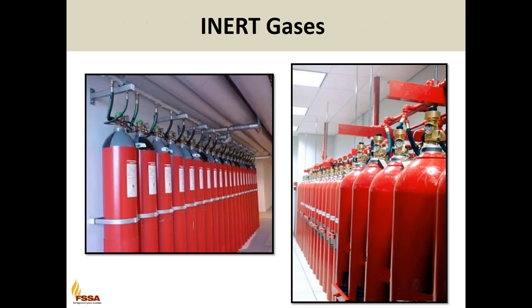With the big push toward green, inert gases have become a good choice as well, as they are the most green of all the clean agents. They are naturally occurring elements in our atmosphere. Inert gases are defined as using one or more of the gases nitrogen, argon, and CO2. The inert gases and blends extinguish a fire by reducing the oxygen concentration to a level that won't allow combustion, but not so low as to be unsafe for occupants.